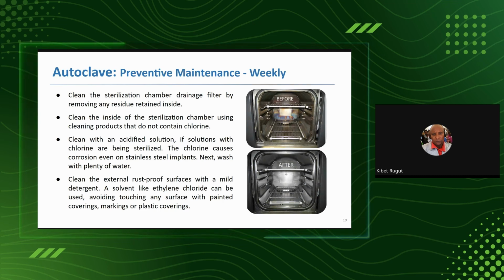So you clean the chamber using cleaning products that do not contain chlorine, and we also use an acidified solution. Usually in the manual, even the percentages of the solution that you use to clean the chambers are provided. Again, you are not restricted in using water, so you can use plenty of water to rinse the system. The external part, usually just use any mild solvent, and clean the external part without deleting or removing the writings that are usually on it.